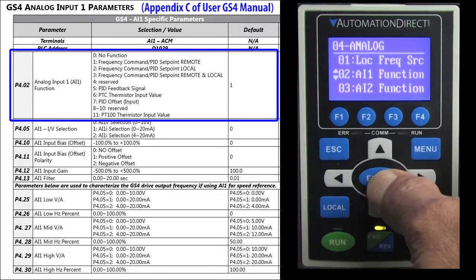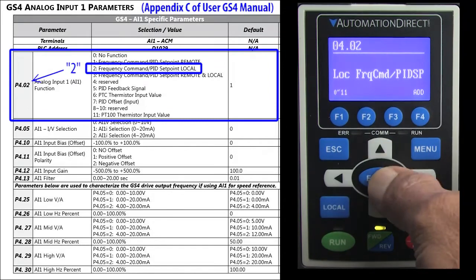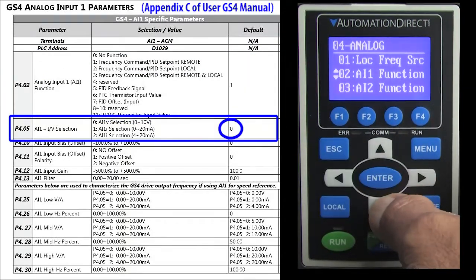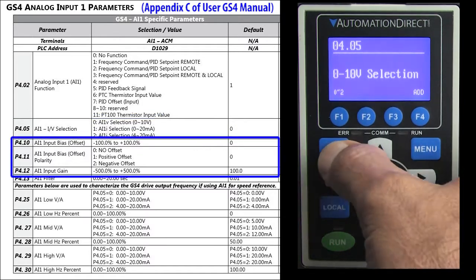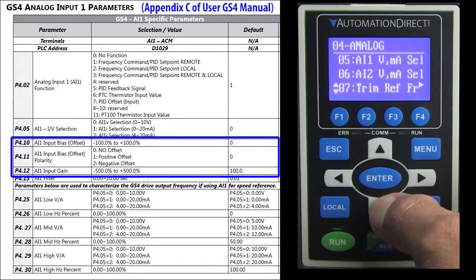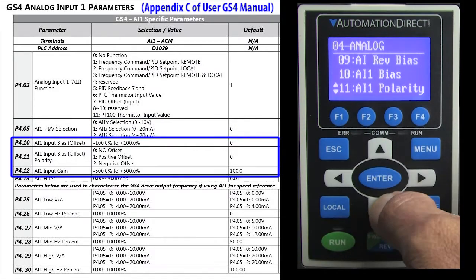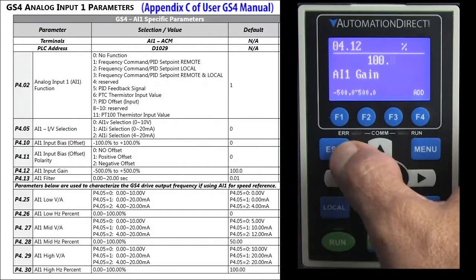First we tell analog input 1 that it is the local frequency source. Analog input 1 defaults to 0 to 10 volts, which is what we want, and we don't want to change the curve with additional bias or gain, so we'll leave those at their default values.